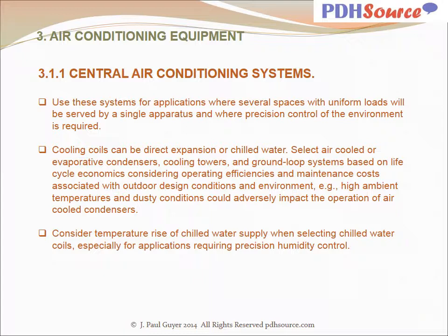And so the term 1 ton of cooling capacity came into use, and it continues to be the standard terminology that's used in the industry these days. 12,000 BTUs, or British thermal units per hour, as far as cooling capacity is concerned, is called a 1 ton air conditioning cooling unit.